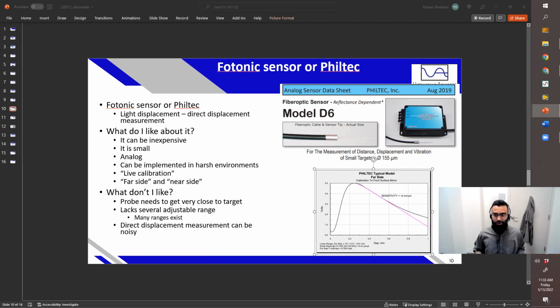So that's the fun part about displacement: you can have a dial. If you want to do a real calibration to double check your manufacturer values, you could dial in 200 microns or so on your precision stage, and you'd be able to verify that indeed, let's say 1 volt of change is going to result in 100 microns or something. So you could actually dial it in and verify that. Yes, with the vibrometer you can't verify. You have nothing to verify with, which is what I don't like about the vibrometer: you have no way of knowing if it's correct. You can't put it next to another system.